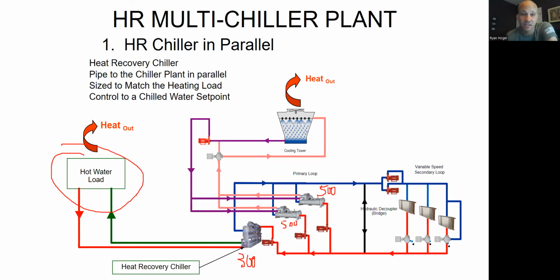I'm going to size this for the baseline heating load. So maybe the whole heating load on the worst case scenario day is 600 tons of heat, but on the least amount of days, it's going to be only 300. I'm going to size this guy for 300, and I'm going to let him put all the hours I can on that. He's going to run year round, nonstop, just shoving heat from this guy to that guy, because I always need 300 tons of heat, and I always need whatever, 3, 4, 500 tons of cooling over here. I'm going to size him for whatever that simultaneous overlap is.